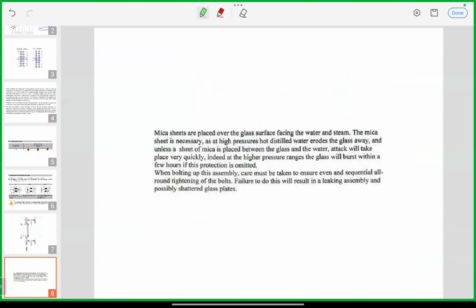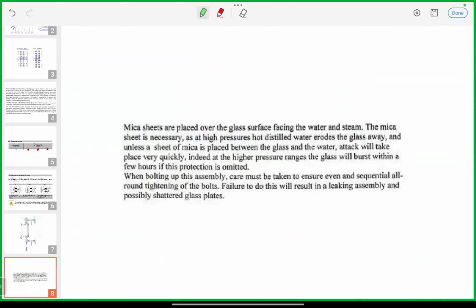What is the function of the mica sheet? The mica sheets are placed over the glass surface facing the water and steam side. The mica sheet is necessary as high pressure hot distilled water causes erosion of the glass. Chemicals added into the glass will together attack the glass and cause damage. To protect the glass from this negative effect, mica sheet has to be provided on either side. Unless a sheet of mica is placed between the glass and water, attack will take place very quickly. Indeed, at high pressure range, the glass will burst within a few hours if the protection is omitted.